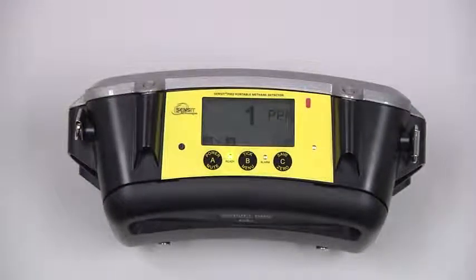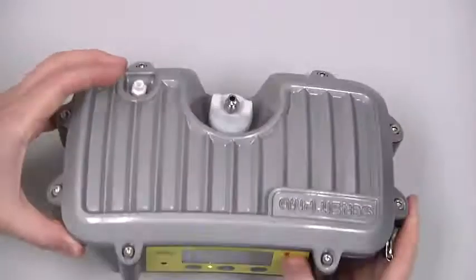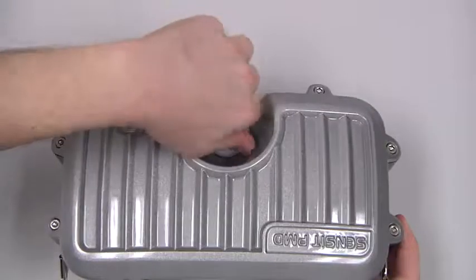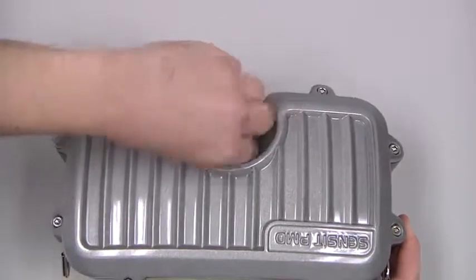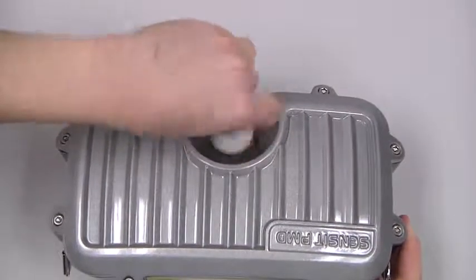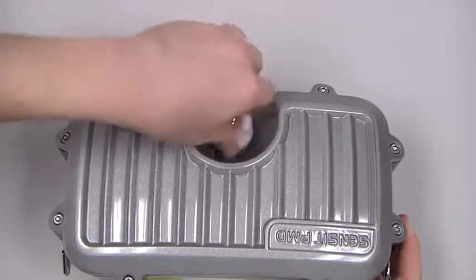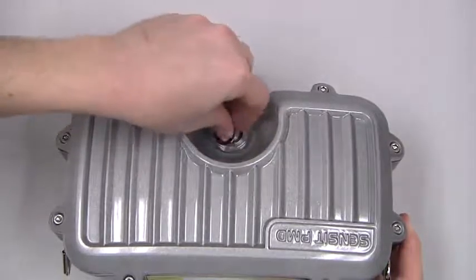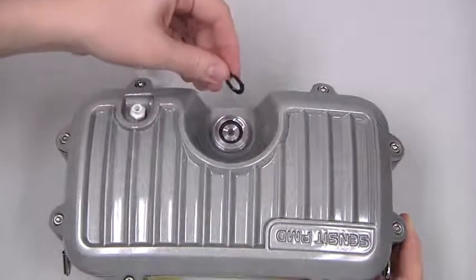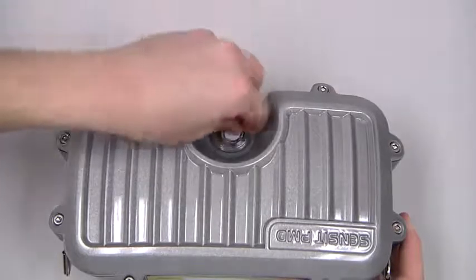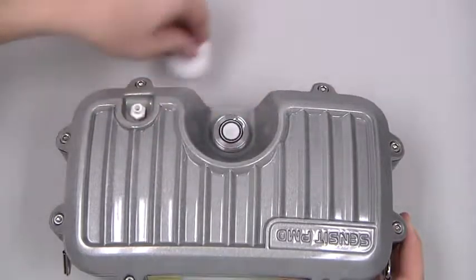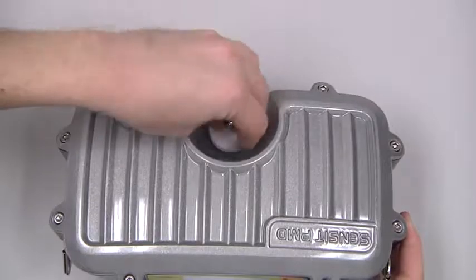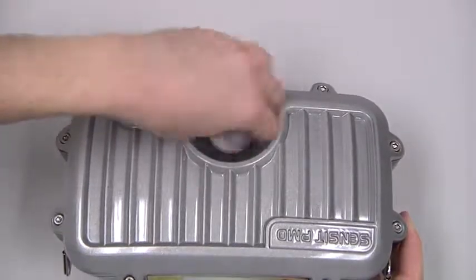Before use, we need to check the integrity of the hydrophobic filter. To do that, we can unscrew the filter cap on the front of the instrument, and take a look at the filter. Ensure that it's not damaged or excessively dirty, and screw the filter cap back on.